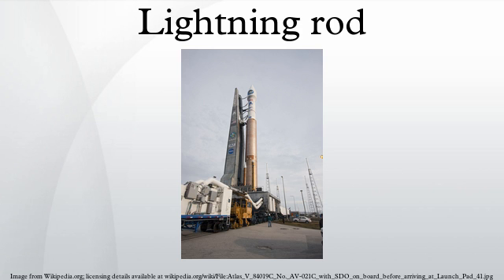Considerable material is used to make up lightning protection systems, so it is prudent to consider carefully where an air terminal will provide the greatest protection. Historical understanding of lightning, from statements made by Ben Franklin, assumed that each lightning rod protected a cone of 45 degrees. This has been found to be unsatisfactory for protecting taller structures, as it is possible for lightning to strike the side of a building.